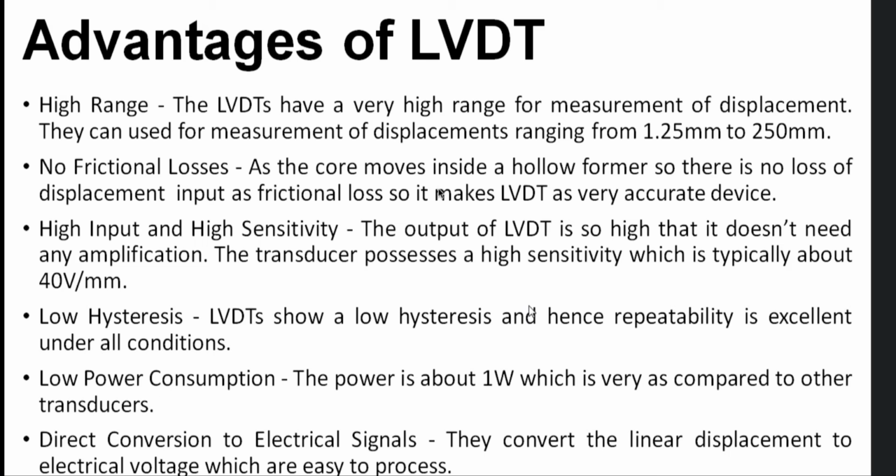The output of the LVDT is so high that it does not need any amplification. The transducer possesses a high sensitivity, typically about 40 volt per millimeter.